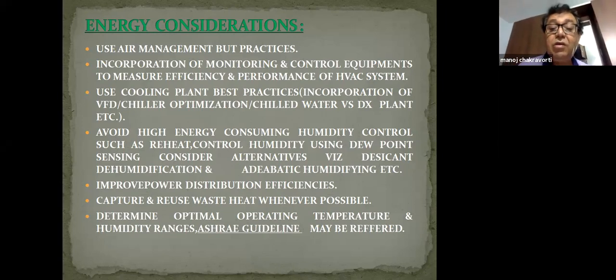Avoid high energy consuming humidity control such as reheat control or humidity control using dew point sensing; consider alternatives such as desiccant dehumidification, adiabatic humidifying, etc. Improve distribution efficiency and capture and reuse waste heat whenever possible.